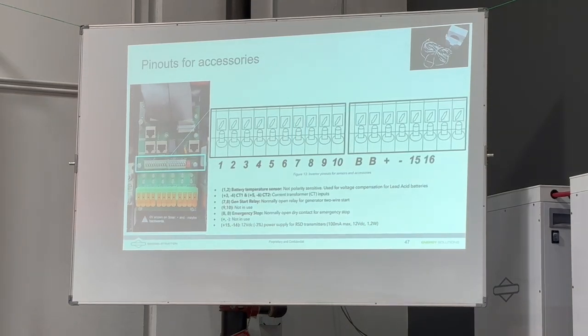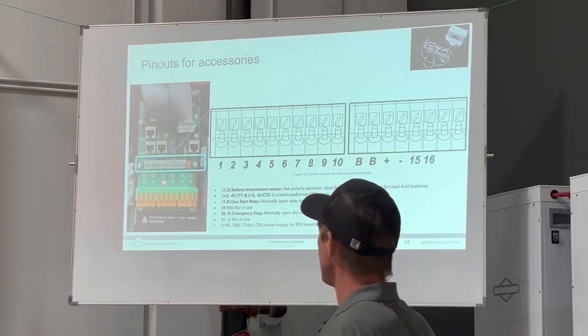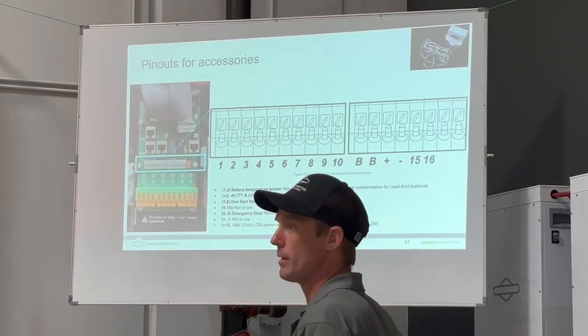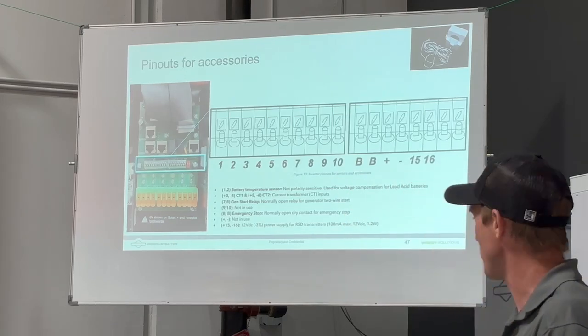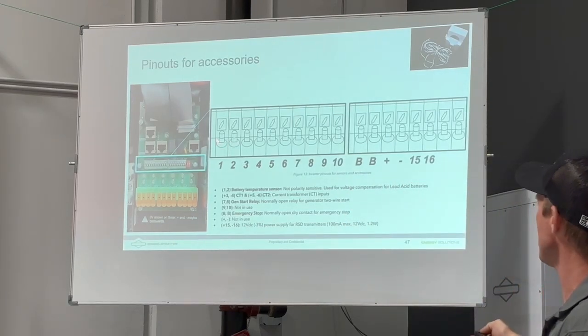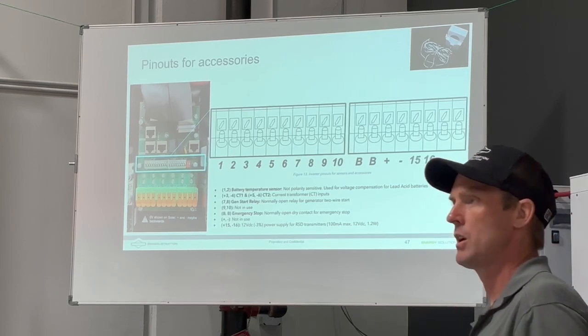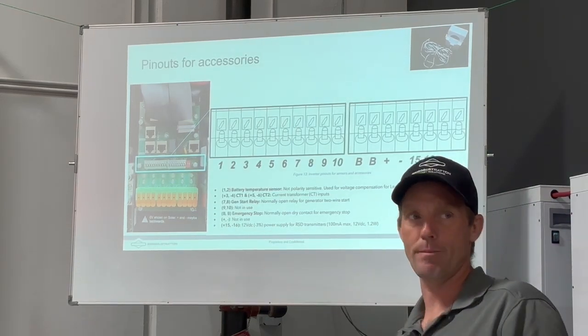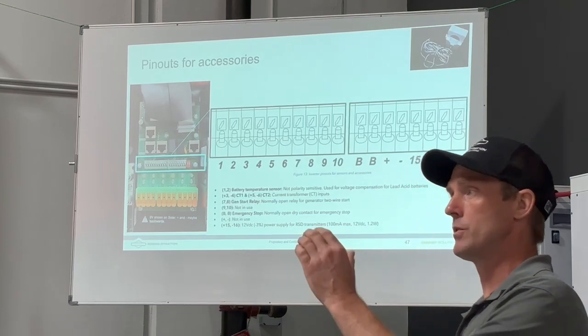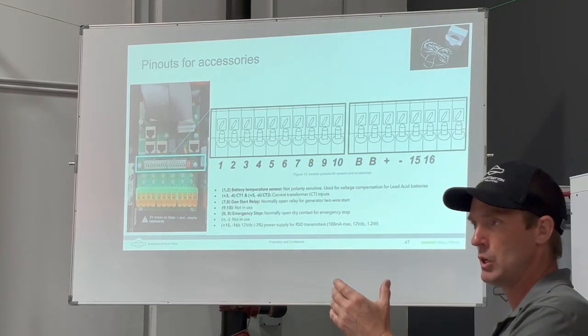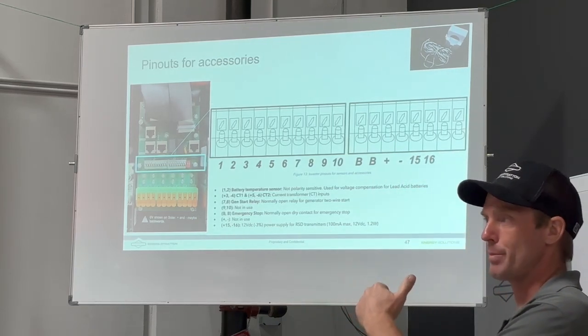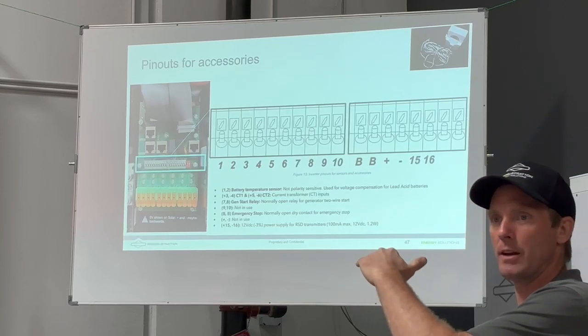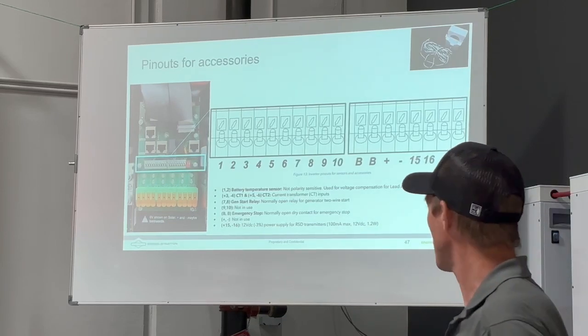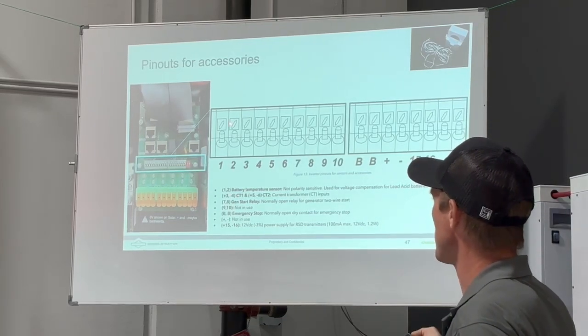Okay, so I promised you I'd break out the pins here on your connections. Remember, I'm going to give you all these slides, so I'm happy to share this with you. So the pin out that's here, you've got a number of things. Number 1 and 2, if you do have a lead acid battery bank, the voltage of a lead acid battery bank varies with temperature and the state of charge. So there's a temperature compensation for lead acid battery bank. So you have to monitor the temperature more closely, and pins 1 and 2 allow you to do that.